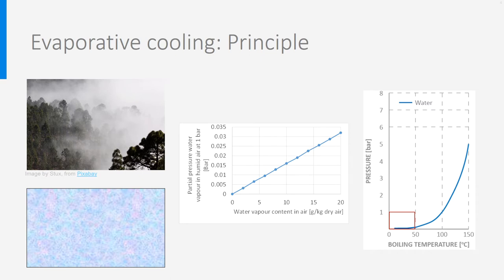If you now remember the boiling curve of water, you see that at these very low pressures, water can boil and condensate at temperatures much lower than 100 degrees, meaning that at room temperature or outdoor temperature, water will evaporate already. And you also have learned that when a fluid is evaporating, it takes a lot of heat from its environment. So, if you inject water droplets in air, it will automatically evaporate because of the low partial pressure, and by evaporating, it will take its needed latent heat of evaporation from the air, which of course will cool down. That is the principle on which evaporative cooling is based.